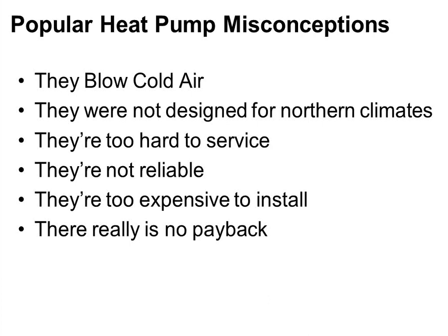I think you're going to find that variable speed units actually have more reliability and longer longevity than standard equipment, if that's a correct statement, I don't know. We've been using variable speed compressors on some of our commercial variable refrigerant flow systems that we've done here at TEC since 2008. And knock on wood, I do not think we've had a compressor failure yet, and those are all variable speed compression. So I think the more variable speed stuff you have, the longer it's probably going to last.